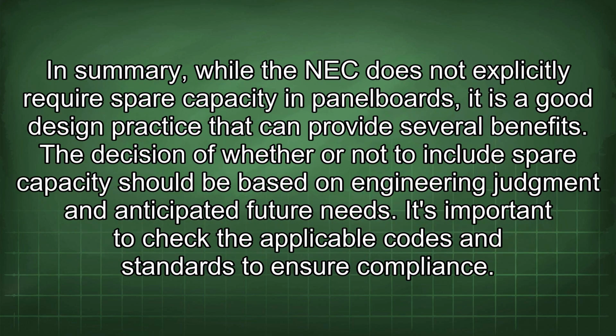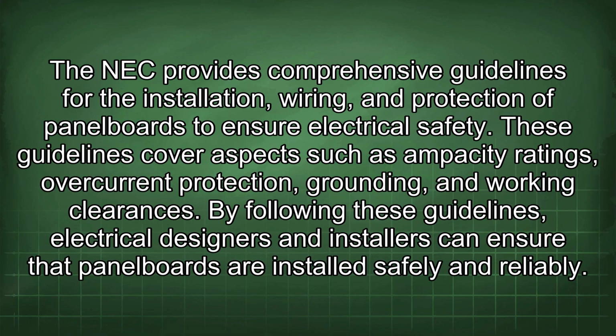In summary, while the NEC does not explicitly require spare capacity in panel boards, it is a good design practice that can provide several benefits. The decision of whether or not to include spare capacity should be based on engineering judgment and anticipated future need. It's important to check the applicable codes and standards to ensure compliance. The NEC provides comprehensive guidelines for the installation, wiring, and protection of panel boards to ensure electrical safety. These guidelines cover aspects such as ampacity ratings, overcurrent protection, grounding, and working clearances. By following these guidelines, electrical designers and installers can ensure that panel boards are installed safely and reliably.